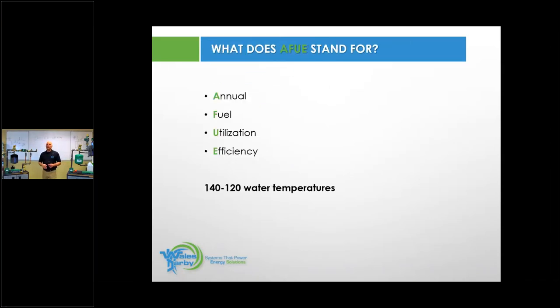Next up, we have the AFUE rating, the annual fuel utilization efficiency. The AFUE rating on boilers is calculated at 140 degree supply water, 120 degree return water. Now, we said earlier, 160, 180 is pretty common for boiler temperatures. So we're not really achieving the efficiencies of the AFUE rating when we're running them at higher temperatures. If we put in a condensing product that says I am 95% efficient, yes, it would be 95% efficient at 120, 140. But if I elevate that to 190, my efficiency comes down. And I think we show a few charts in here throughout the program to back that up.